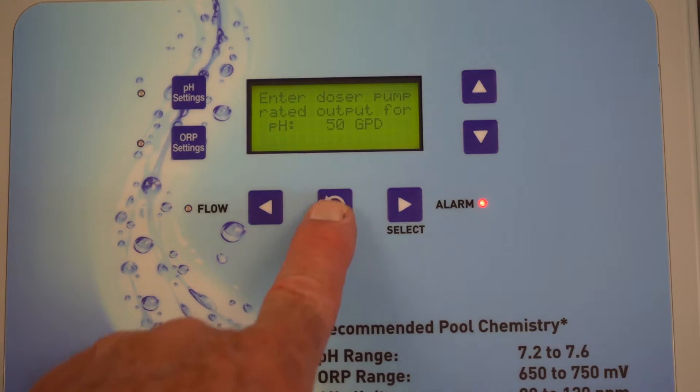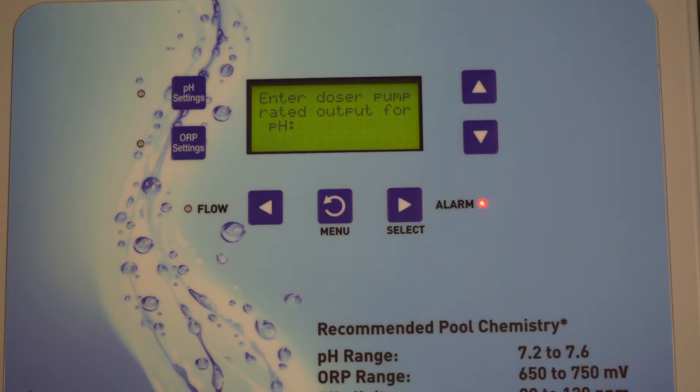Once we have that, hit the menu button. It asks for the doser pump rated output and says 50 gallons per day. Technically that is misleading — originally Pentair used a number five tube on a Stenner pump that put out 50 gallons per day. They later found the reliability was low and switched to a number two tube, which only puts out 10 gallons per day. However, when they re-revised the software, the 50 gallons per day setting is the correct entry for the number two tube — it will do the proper calculations.